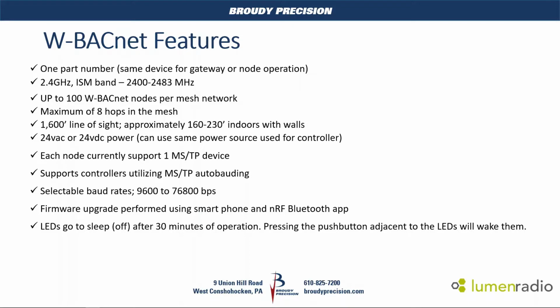If the controller is an auto baud type of controller, that is supported with the W-BACnets. Those devices will set the baud rate for the controller, and there are no issues with that. The node does not count as a MSTP device, nor does the gateway. You have selectable baud rates from 9600 to 76800. So pretty much any baud rate that MSTP uses, you can select and have these nodes set up for that.